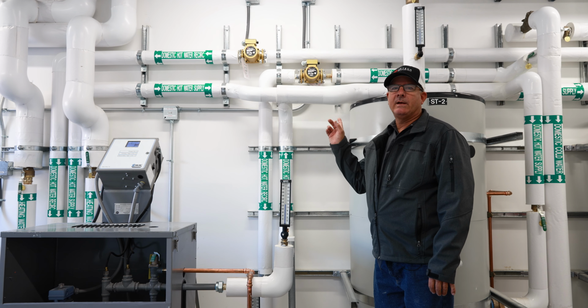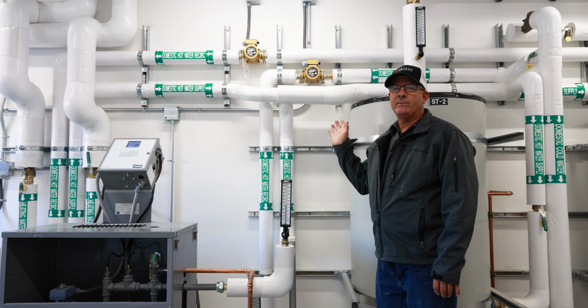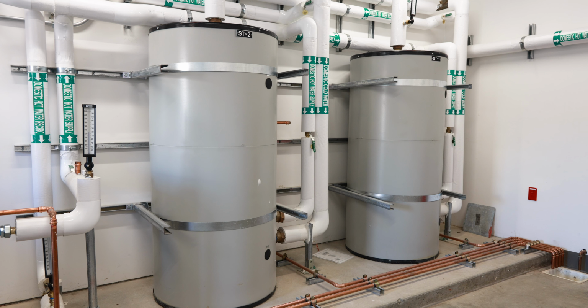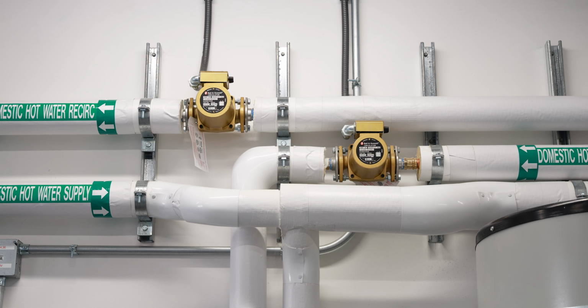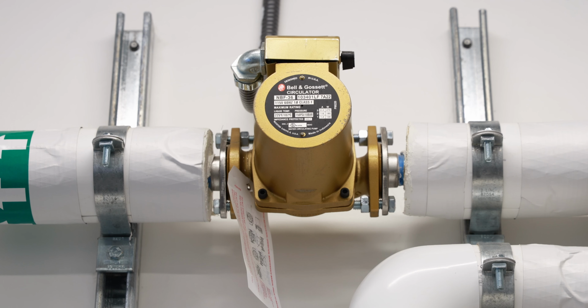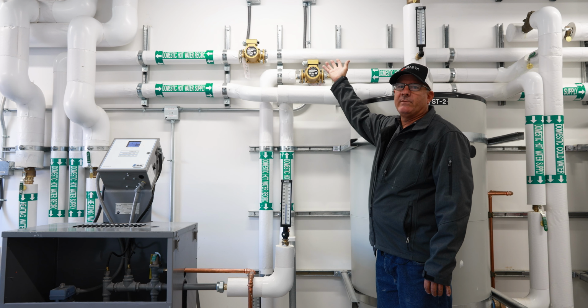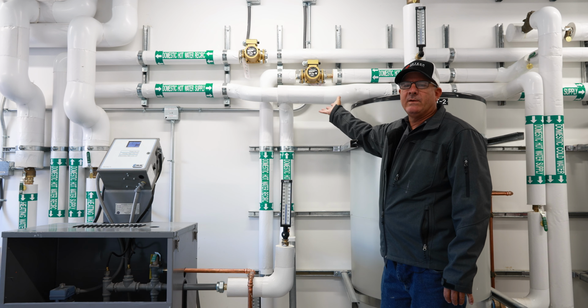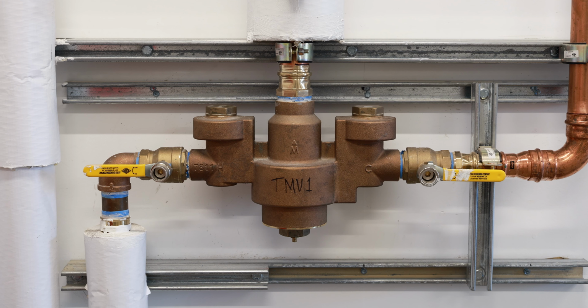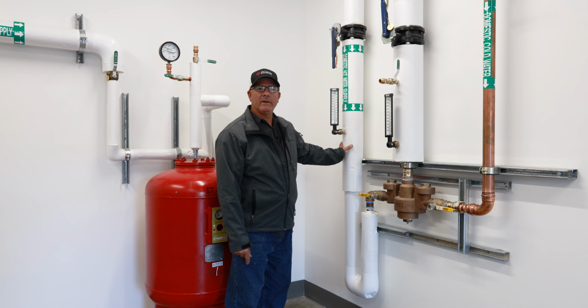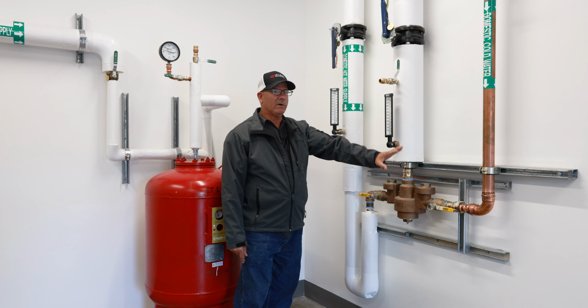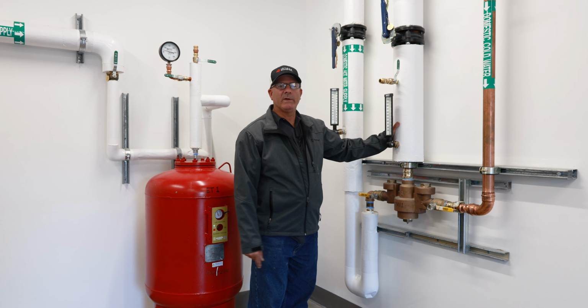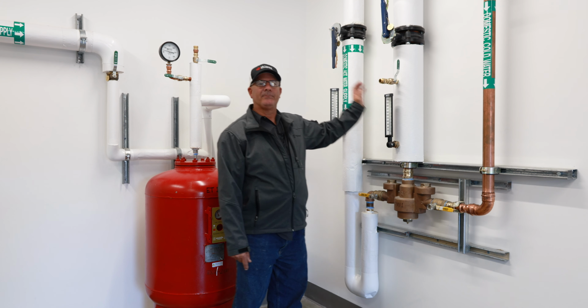So we're back at the hot water circulating pumps. These pumps are what's circulating the water from the storage tanks through the heat exchangers. They have speed controls on them. Once again, these have already been set and determined to run at high speed. There's disconnects right above them. Once again, redundant. This is your water tempering valve, mixing valve. We have hot water in at 130 degrees, cold water this side, 120 degrees going out to your building.